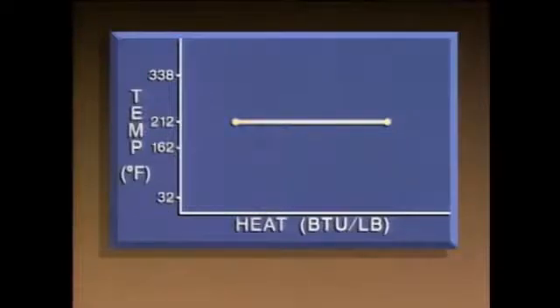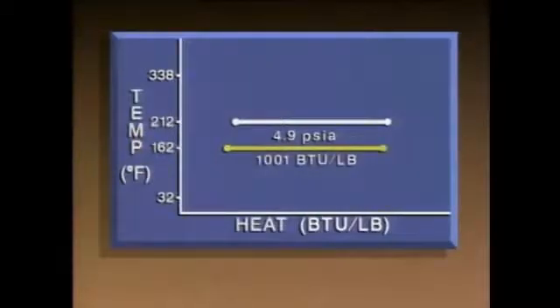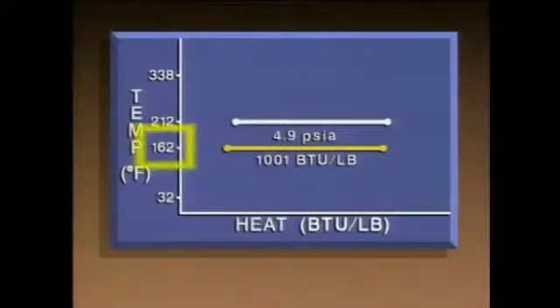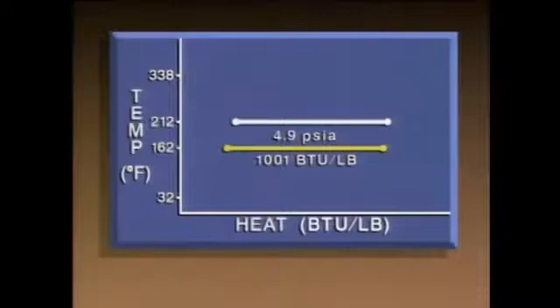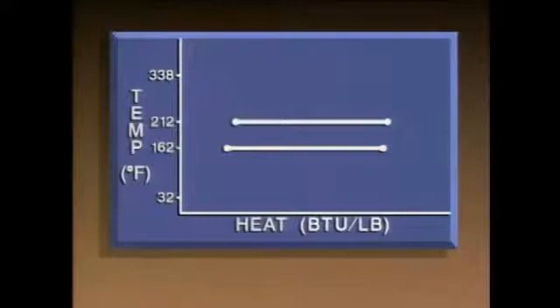Now let's take an example in which the pressure is less than atmospheric. At 4.9 PSIA, a pound of water boils at 162 degrees Fahrenheit, and the latent heat of vaporization is around 1,001 BTUs per pound. So when the pressure is reduced, water boils at a lower temperature, but it takes more heat to boil all the water into steam. At lower temperatures, water molecules move more slowly, making it harder for them to escape as steam.